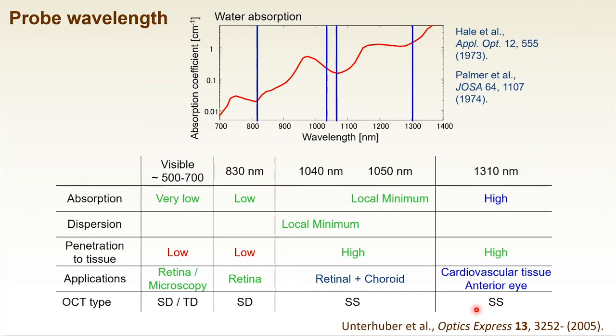Looking at the near infrared region: 830 nanometers is sometimes visible as red light, but sometimes not — it's nearly the border between visible and infrared, so we call it near infrared. At 1040–1050 nanometers, we cannot see it. At 1310 nanometers, we call it eye-safe. OCT normally uses one of these three bands: 830 nm, the one-micron band around 1040–1050 nm, or 1.3 microns.